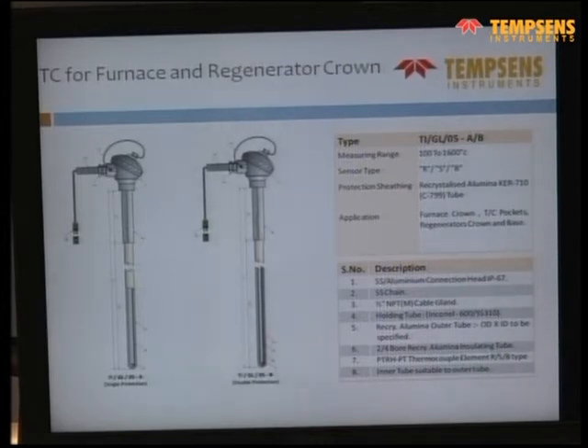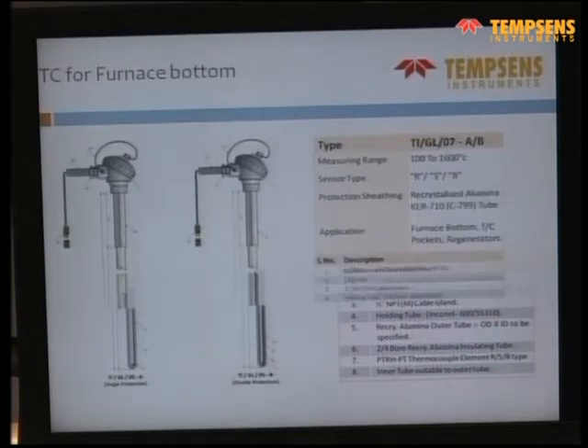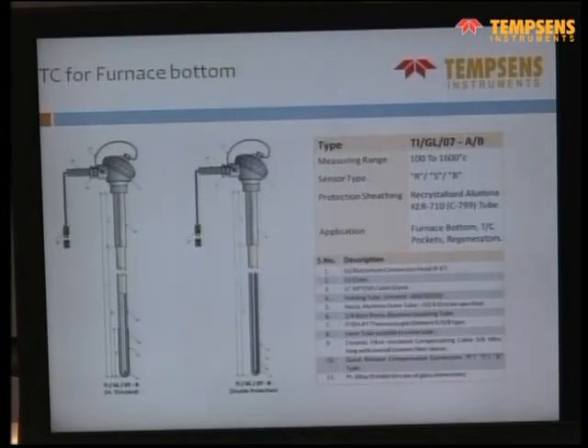So this is a double ceramic tube, which is a simple thing, single or double ceramic tube. At the furnace bottom, sometimes they are having only the ceramic, which is inside the refractory itself. It is not touching the glass, but in case over a period of time, maybe 3 years, 5 years, the refractory will be worn out. So they have a small platinum thimble, a small platinum cover, as you see in the left hand side picture. So even if the refractory is corroded, the thermocouple tip would still be made of platinum, so it will be still intact, and the thermocouple will still give the temperature.